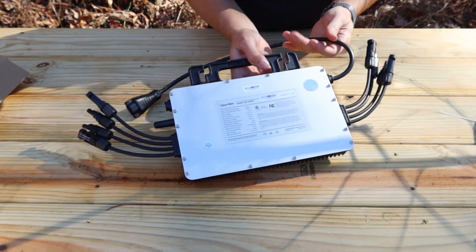We flip this over — it's got some data back here. This is the Hoymiles model HM-1500NT. The range of input operating voltage is 16 to 60 volts DC. The range of peak power or MPPT voltage is 33 to 48 volts, which pretty much means it's designed for your typical solar panel that's about 250 to 260 watts. The max input current is 11.5 times four, and the max input short circuit is four times 15 amps. The nominal output voltage is 240 volts AC, the max continuous output current is 5.99 amps AC, the nominal output frequency is 60 hertz, and the max continuous output power is 1438 volt-amps.